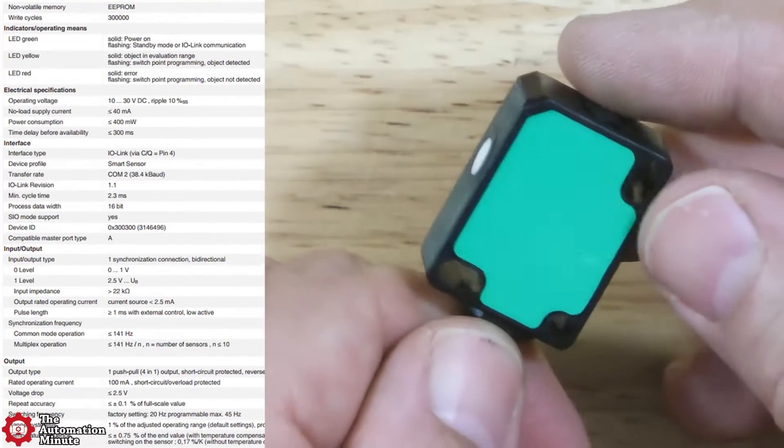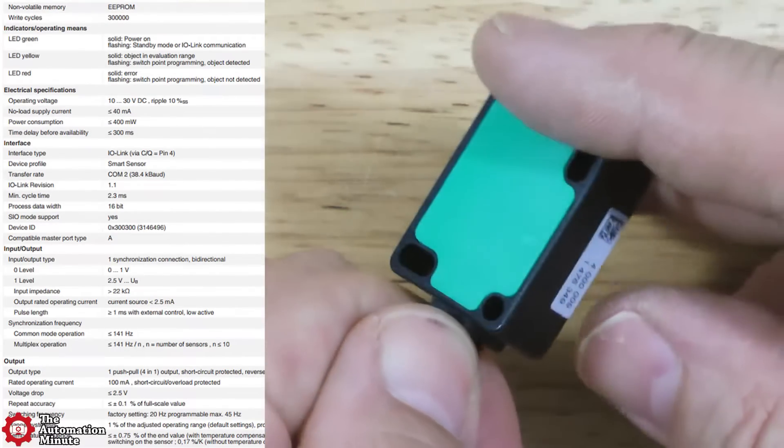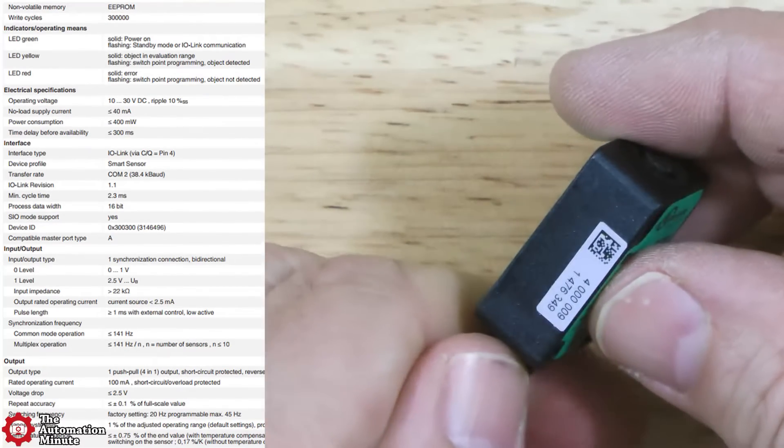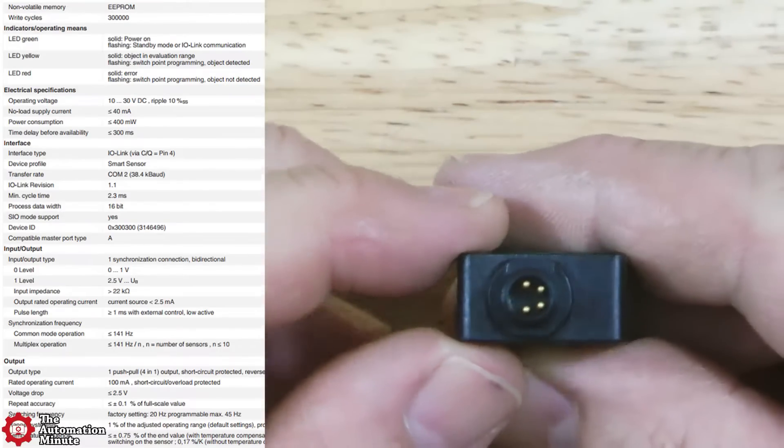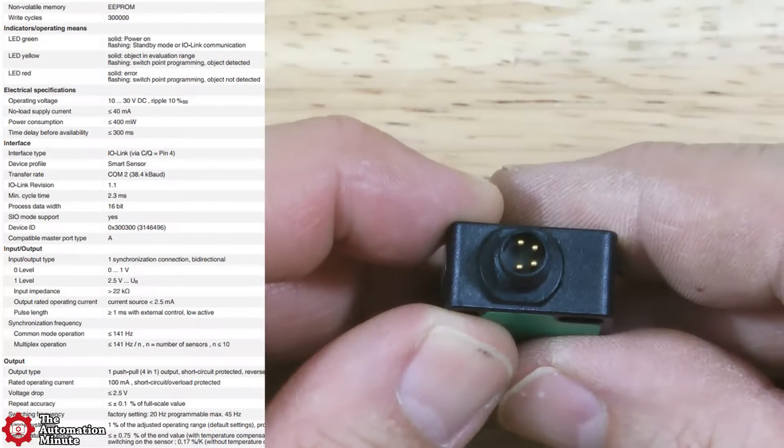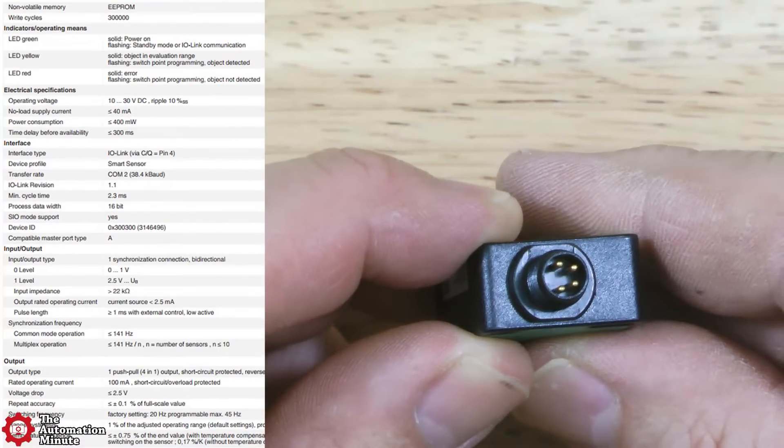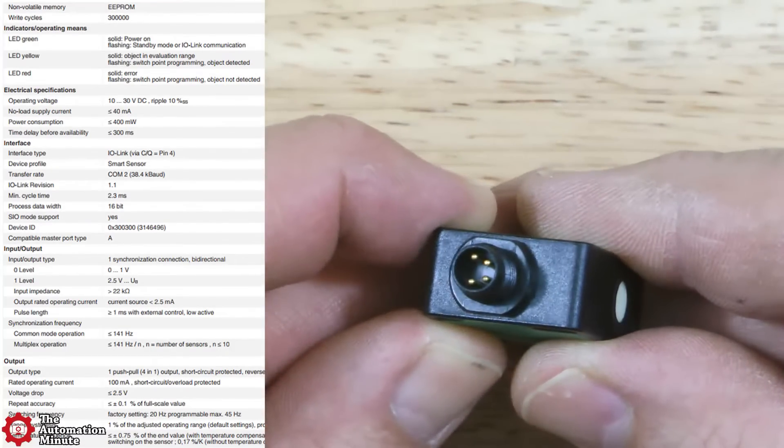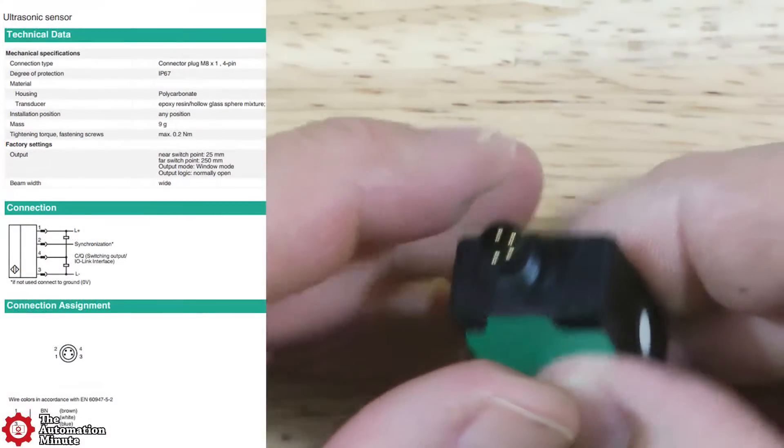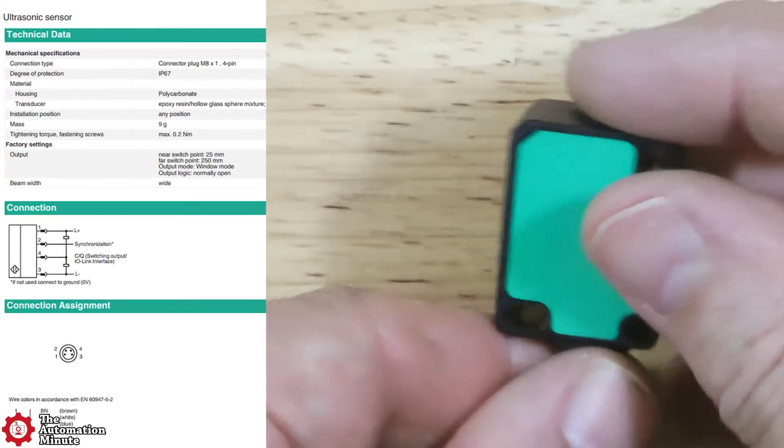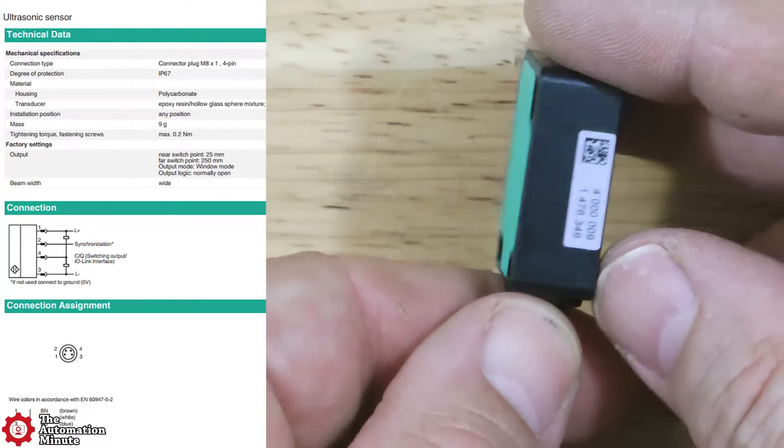Its rated operating current is 100 milliamps, and this is also short-circuit and overload protected. This model also supports IO-Link REV 1.1 and has a 4-pin M8 connector plug.